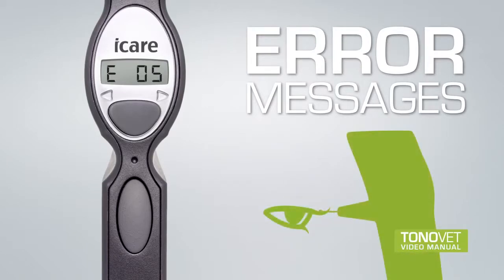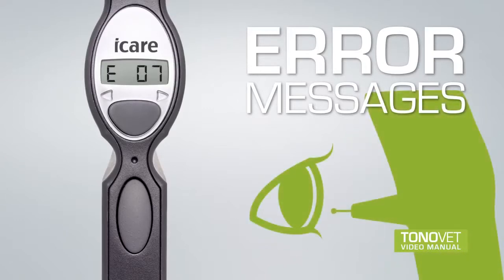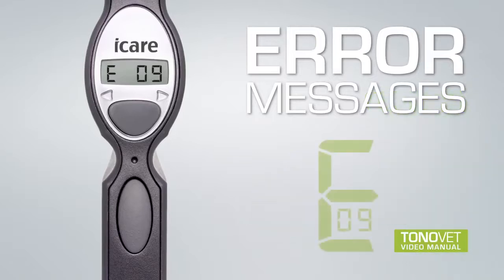E05 indicates the hit was too soft, most likely because the probe hit the eyelid. Repeat the measurement. E06 indicates the hit was too hard, most likely because the probe hit the opening eyelid or calcification in the cornea. Repeat the measurement. E07 indicates a bad bounce because the probe did not hit the central cornea. Repeat the measurement. E09 indicates an erroneous measurement for a reason other than those described, with E01 to E07.